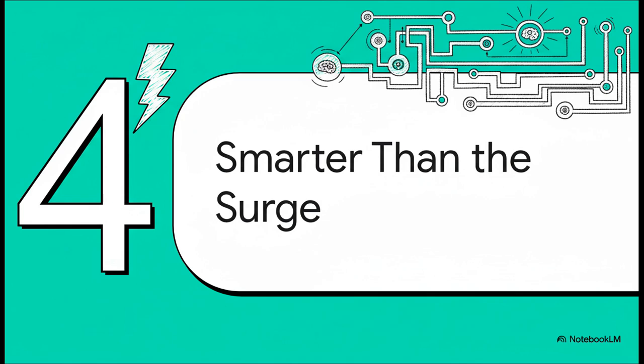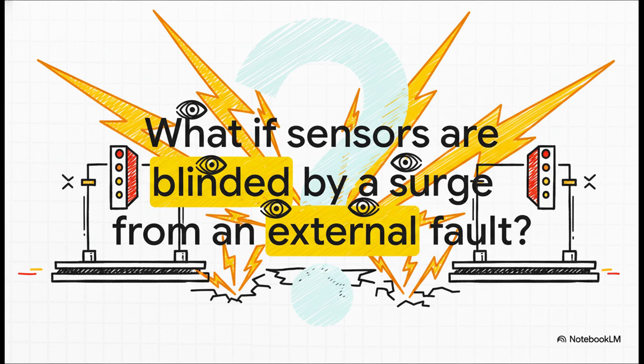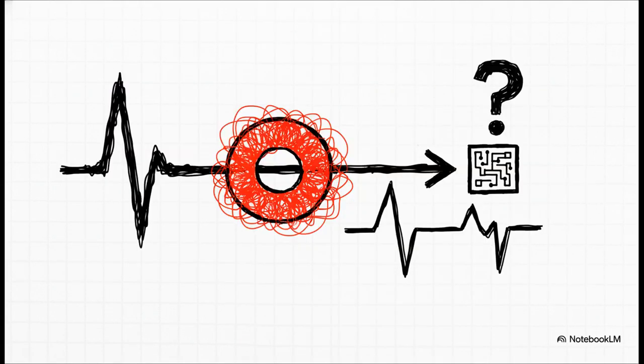But of course, there's a tricky complication that makes these systems even more impressive. They have to be smarter than the surge itself. So this brings up a really critical question. What happens if a massive fault outside the zone is so powerful that it temporarily blinds the sensors that are measuring the current? Could the whole system get tricked into shutting down when it shouldn't? Well, this challenge is called current transformer saturation, or CT saturation. Think of it like this. That massive external surge is like a deafening noise that completely overwhelms the sensors. For a split second, they just can't report the current accurately, and they might accidentally hear an imbalance that isn't really there. And this could fool the relay into causing a huge, unnecessary shutdown.